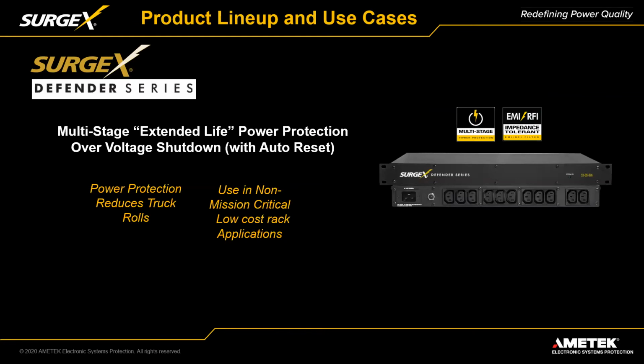The Defender series. As I mentioned with the Envision product, we brought that over from our sister brand, ESP. It's all the same company. The ESP line has a little different technology for surge protection. It's actually MOV-based, but it's a hybrid circuit using MOVs, gas tubes, and TVS diodes working together in a patent-protected circuit, which removes some of the detriments of purely MOV-based surge protection. We're not susceptible to overvoltages, and we have a much longer life expectancy because when a surge occurs the gas tube takes the brunt of the energy, not the MOV. So the MOV lasts a lot longer. We call this an extended life MOV-based product.